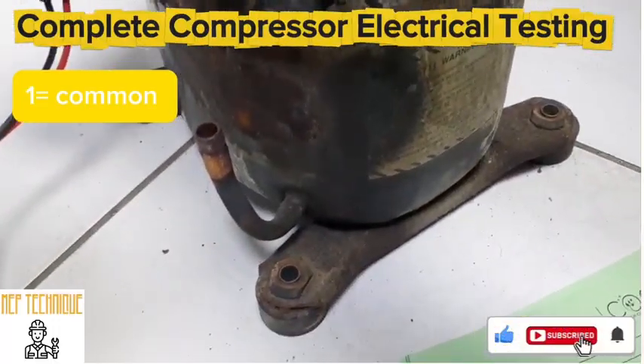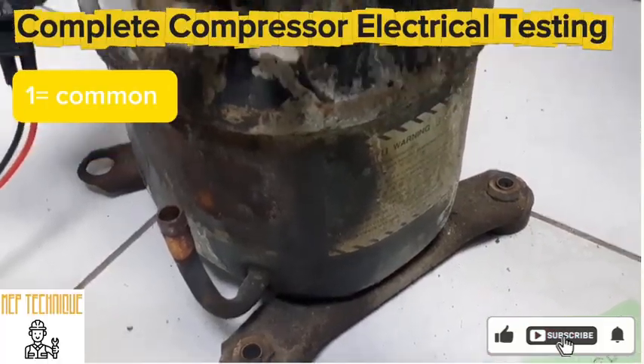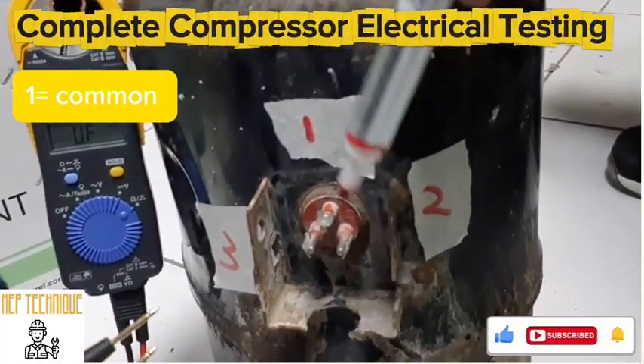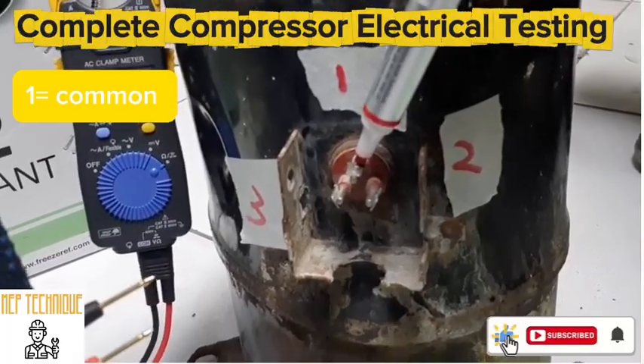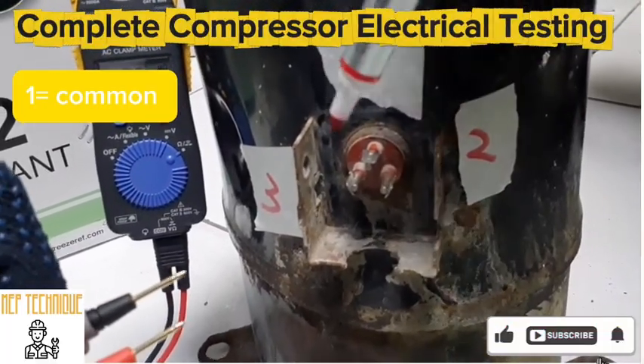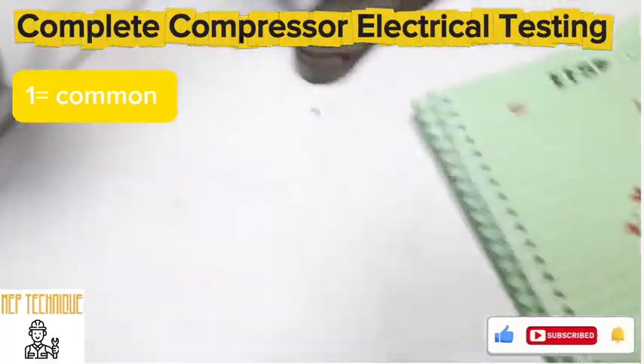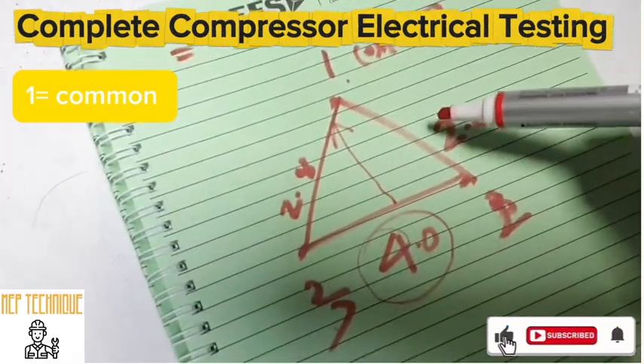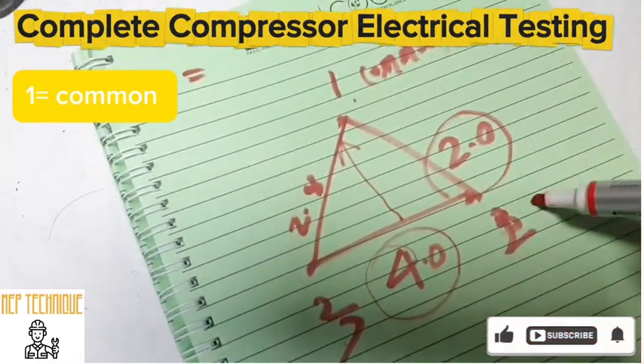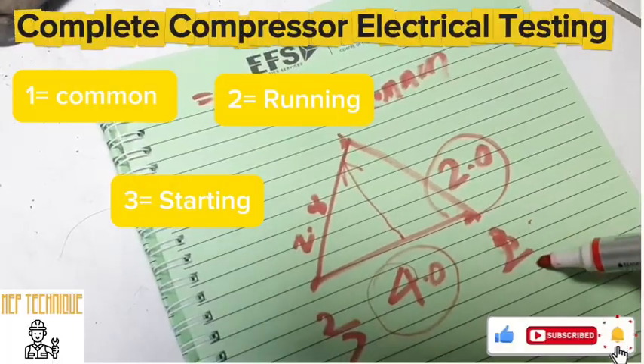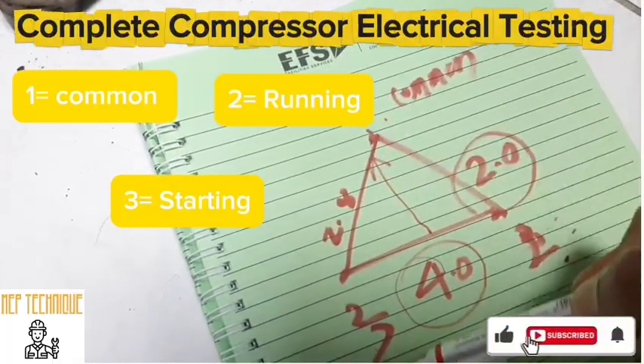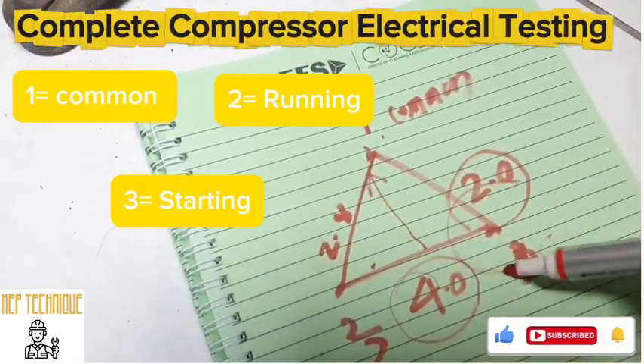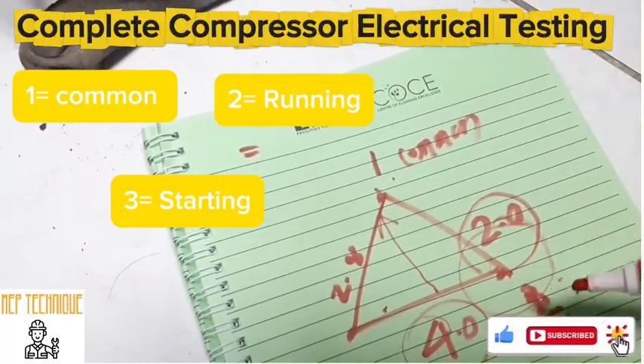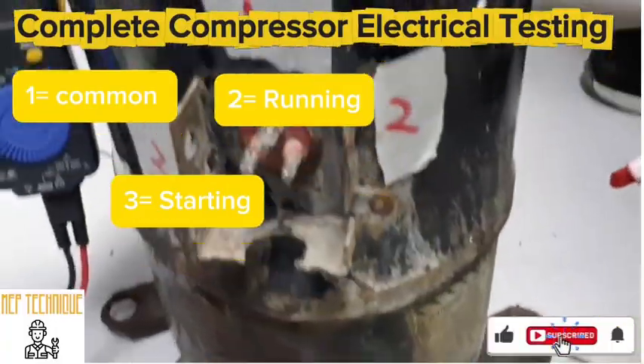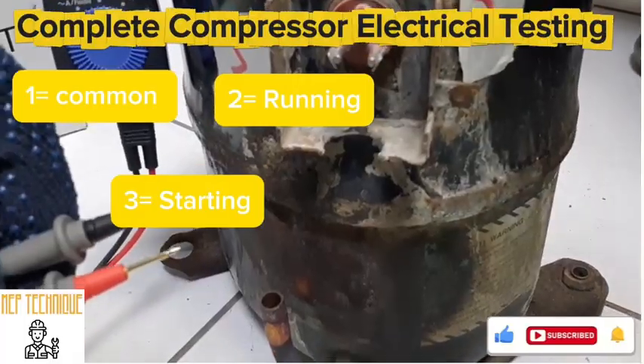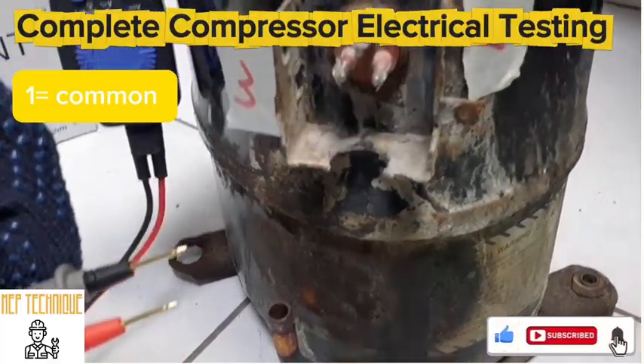Always the highest resistance should be between the running and starting terminals, 2 to 3. Once we have the common, running is the lowest and starting is the medium. Here you can see the lowest resistance, common to 2, is 2.0, and common to 3 is 2.8. The lowest resistance should be running and the medium should be starting. So in this condition, we have identified common, running and starting.